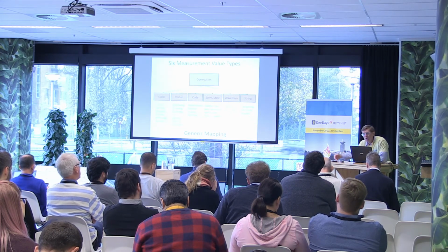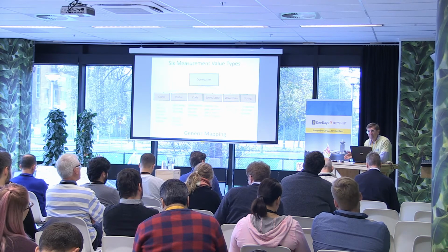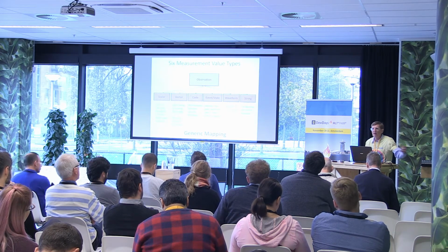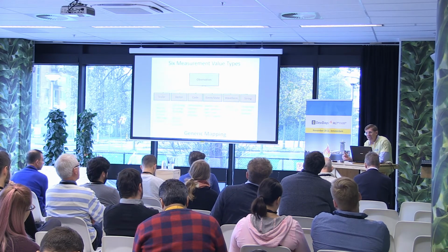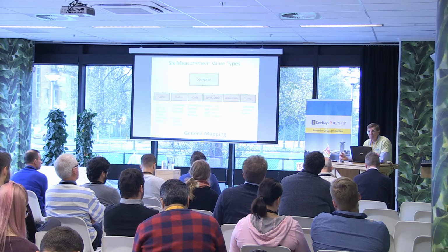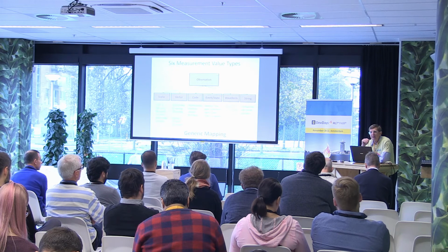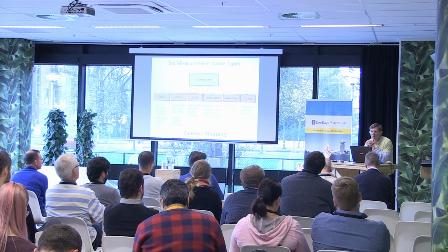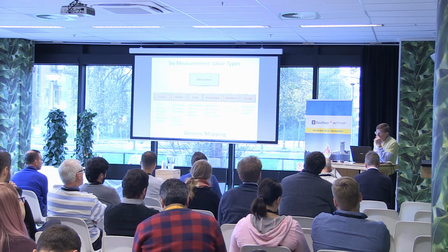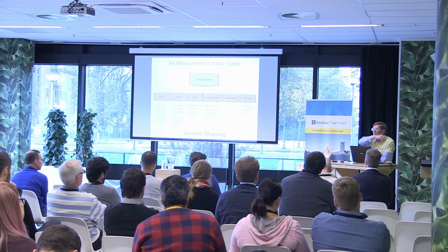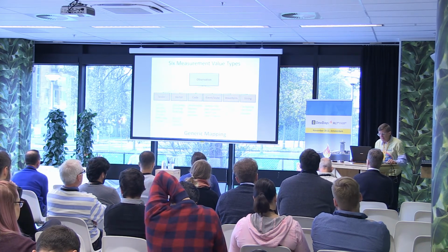I want to make sure that when they get a new device, I don't have to make a new map. Or say a new specialization comes out, and I don't have a map for all those new LOINC codes. What do I do? It's totally non-future-proof. So the whole concept is that the PHG does not have to know anything. It is pure dumb. All it does is take the structure that it gets from the device, uses that device information, and converts it to FHIR. Now, clearly on the read end, when you read those codes, you have to know what they mean. So when the codes get updated for a new device, you have to do it on the read end. But for the PHGs out there in the field, all over the place, you don't. So that's a very important part of this generic mapping.